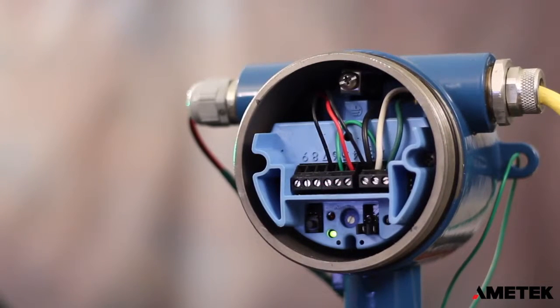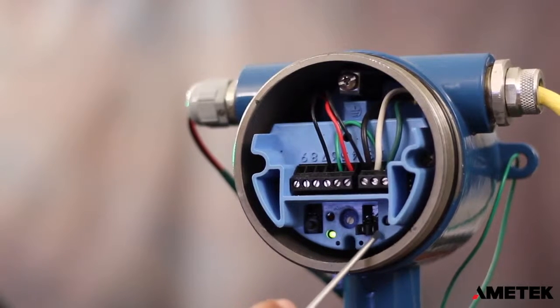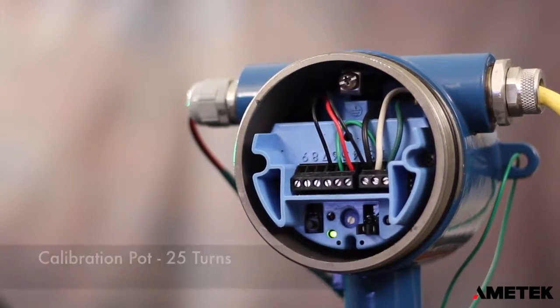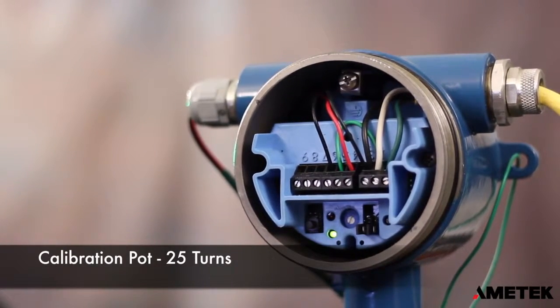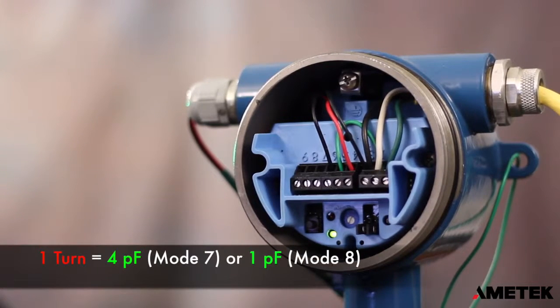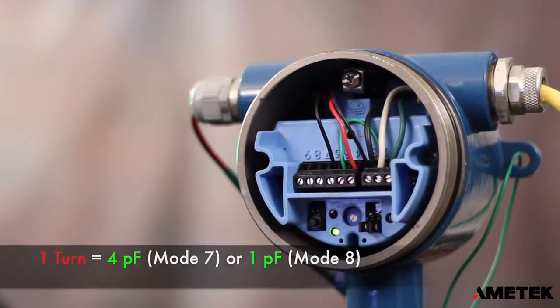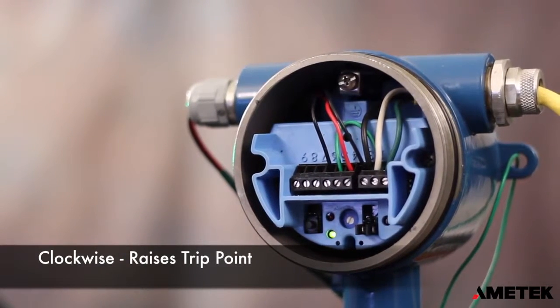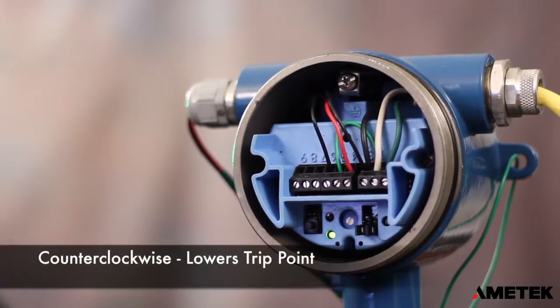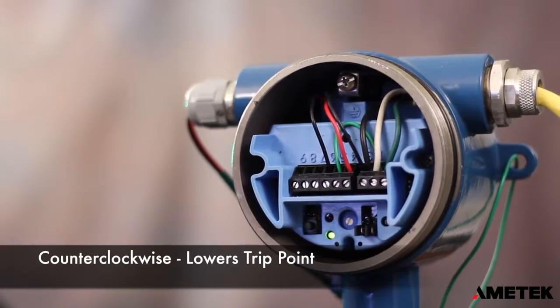Now to do the calibration, you're going to be using the sensitivity adjustment pot located on the electronics module. Full range of the pot is 25 turns. Each rotation of the pot changes the operating point by 4 picofarads in mode 7 or 1 picofarad in mode 8. Turning the adjustment clockwise will raise the level at which the relay operates, making it less sensitive. Turning the adjustment counterclockwise will lower the level at which the relay operates, making it more sensitive.